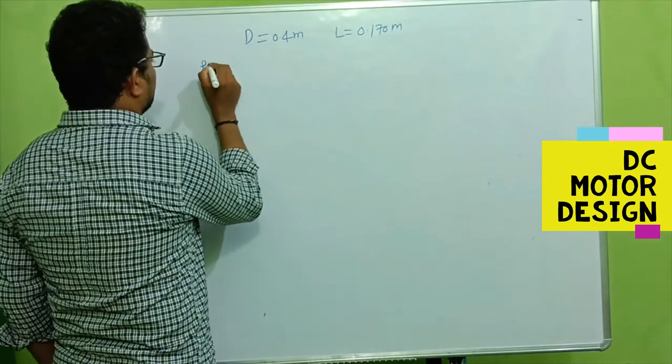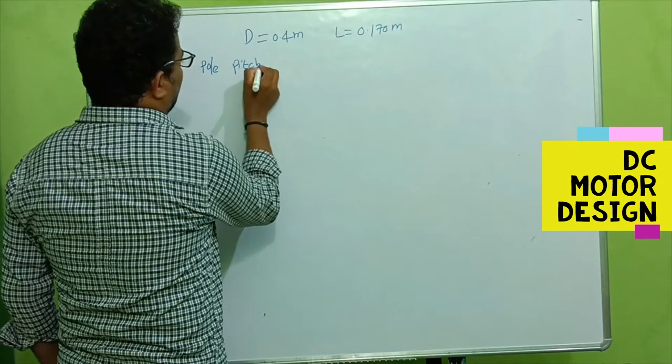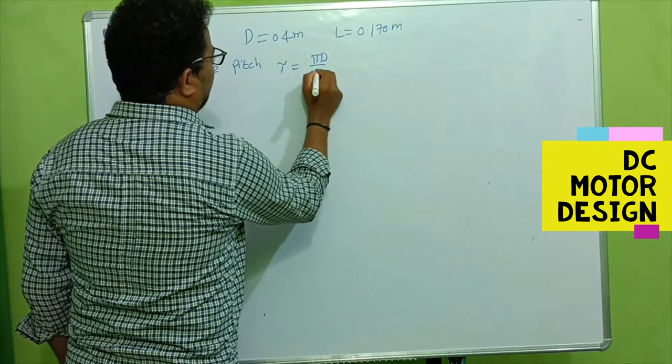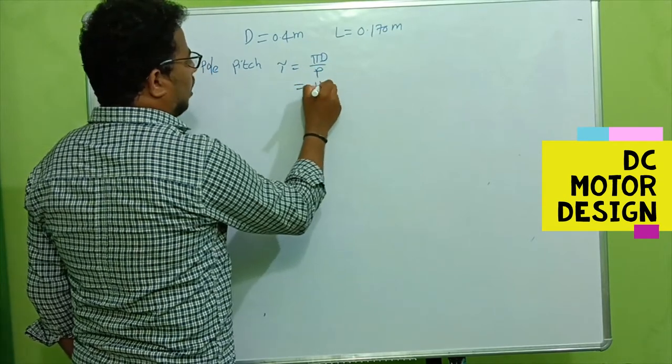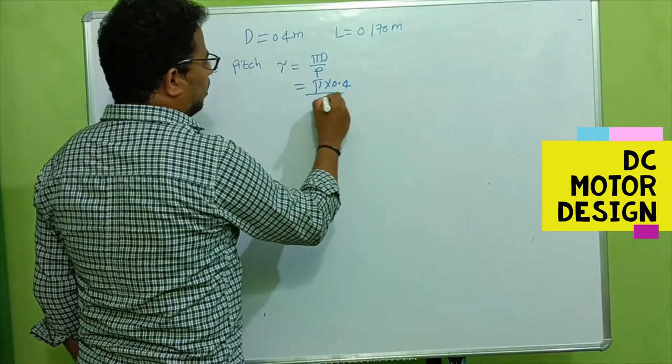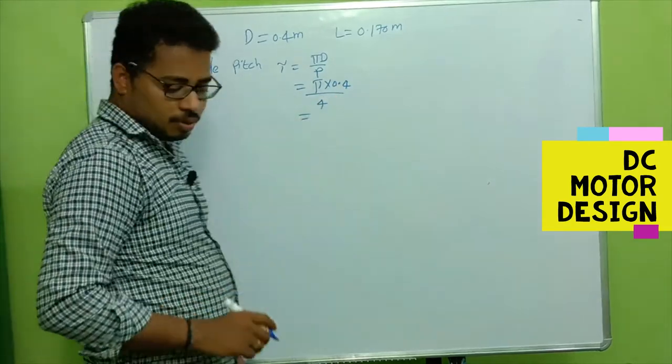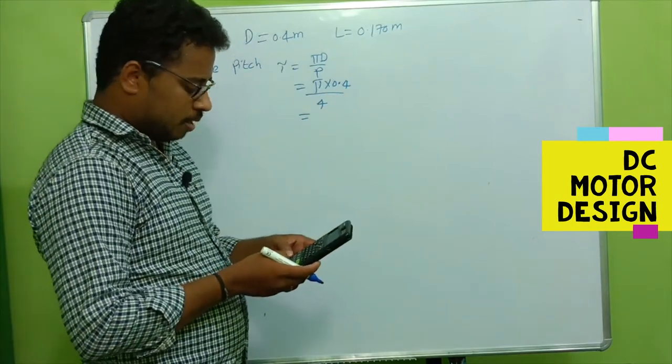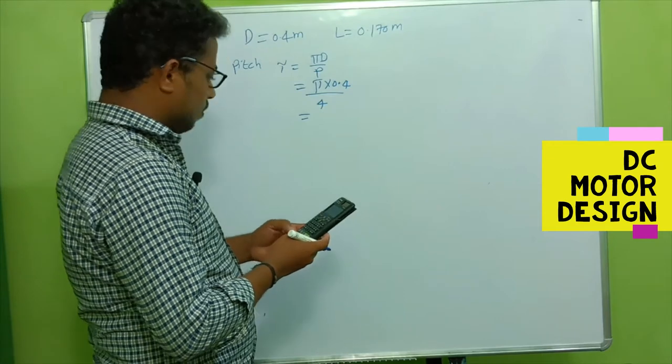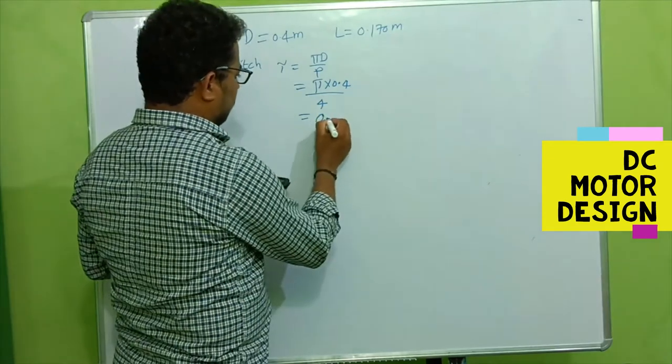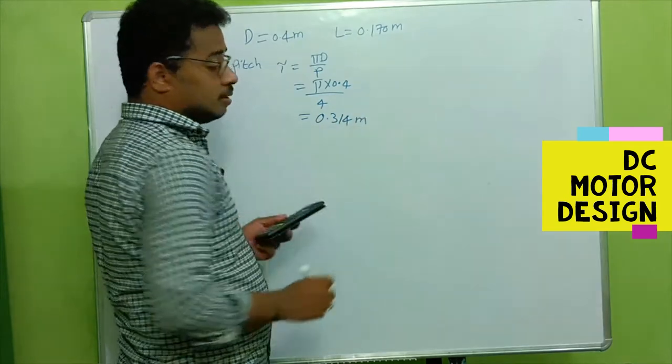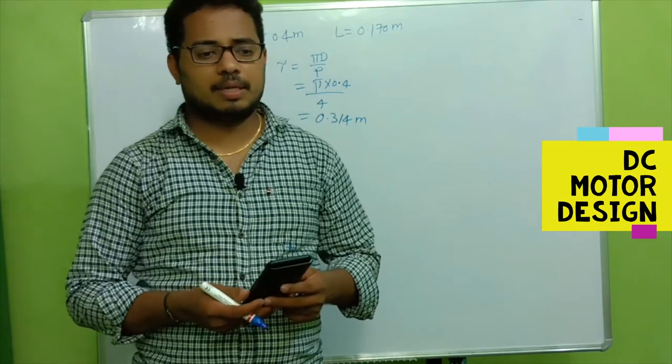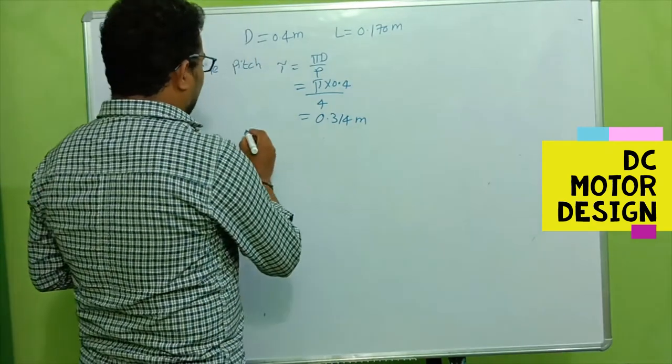First, let's calculate the pole pitch. Pole pitch is the pole center to center distance, denoted as τ (tau). That's π times D divided by number of poles. We have π times 0.4 diameter divided by 4 poles, which gives us π times 0.4 by 4, so we get 0.314 meters. So 0.314 meters is the pole pitch for us.